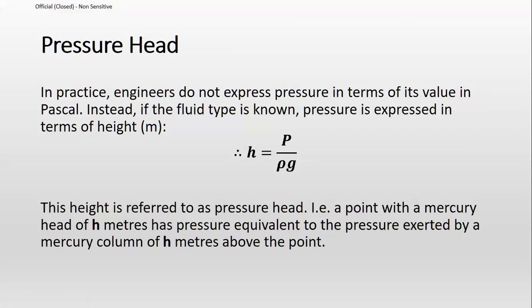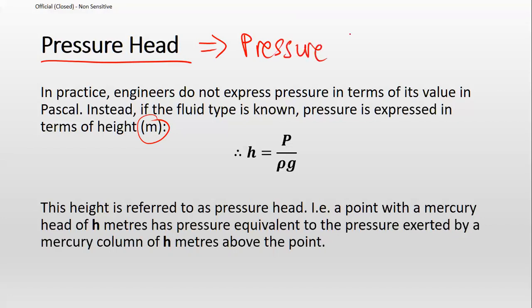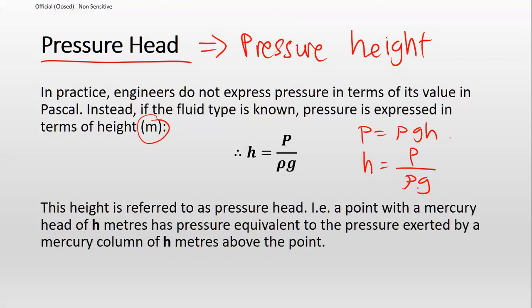In the industry, we seldom express pressure as a direct value like bar or kilopascal. Instead, we usually relate pressure as a form of head, with units in meters — sometimes called pressure height. We derive this from P = ρgh by rearranging: H = P / (ρg). We associate the pressure with height.